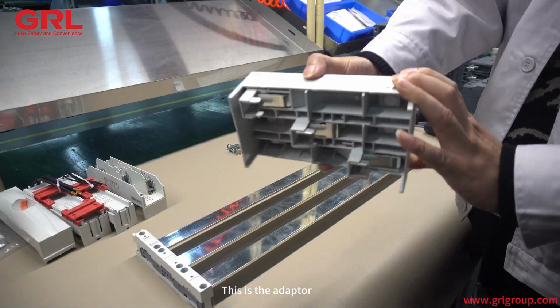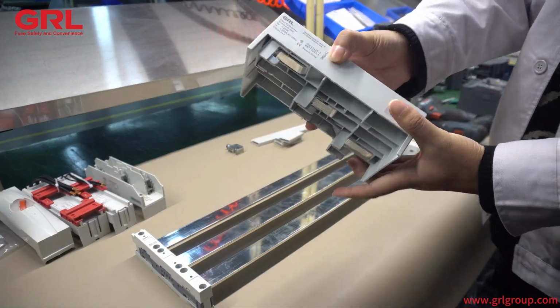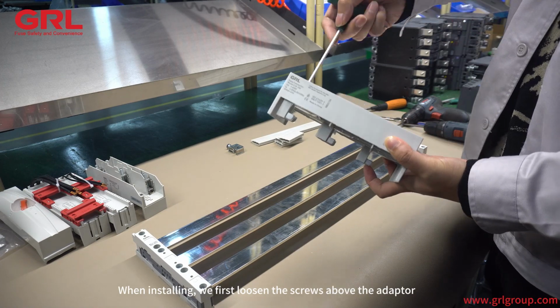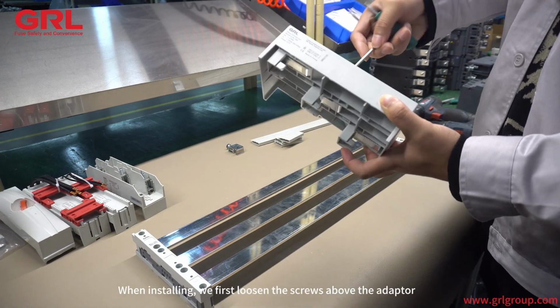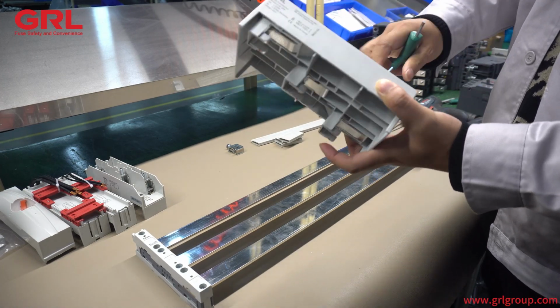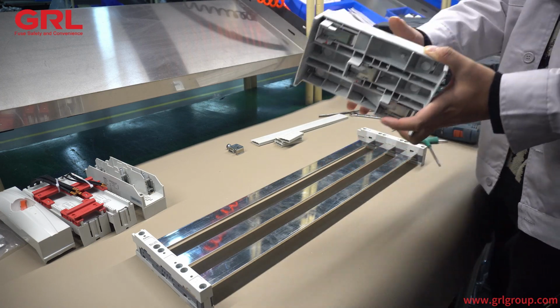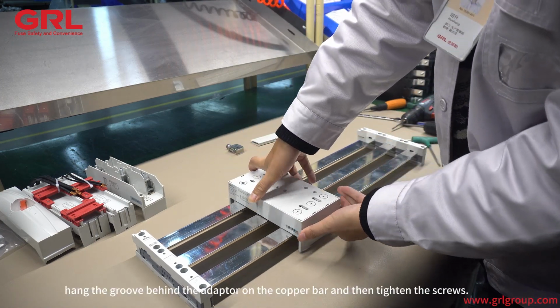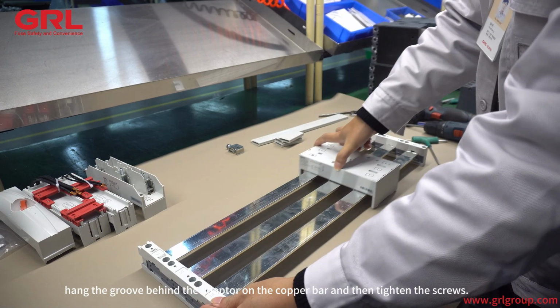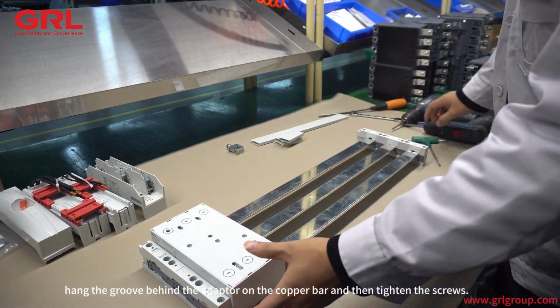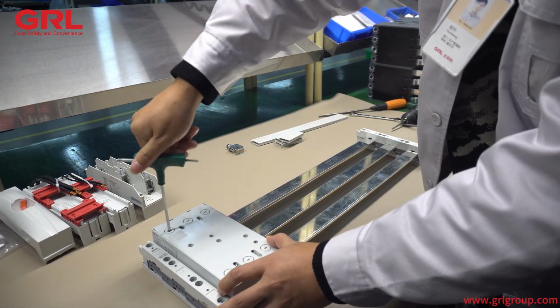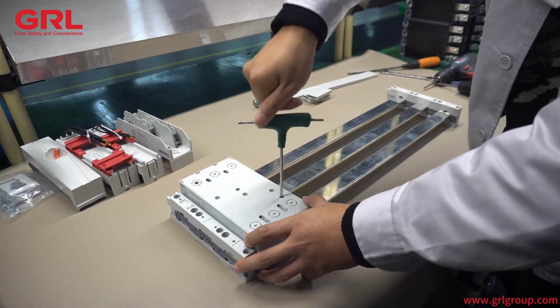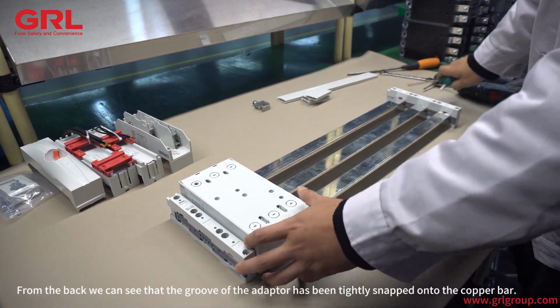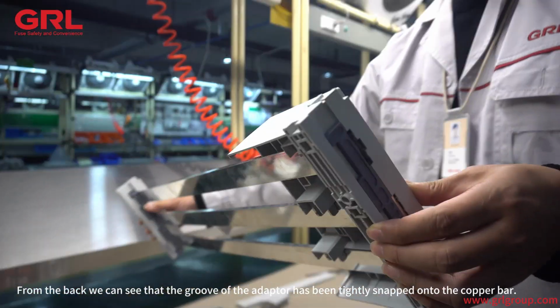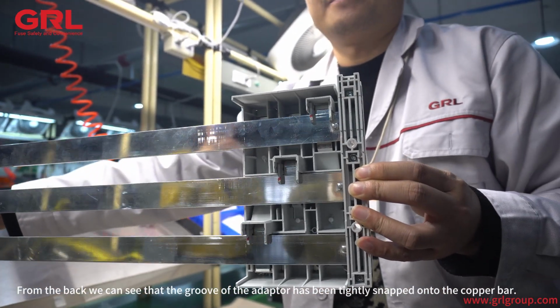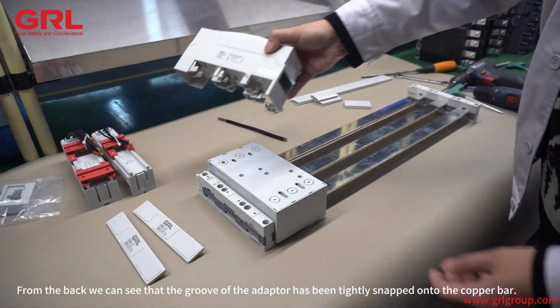This is the adapter. When installing, we first loosen the screws above the adapter, then hang the groove behind the adapter on the copper bar and tighten the screws. From the back we can see that the groove of the adapter has been tightly snapped onto the copper bar.